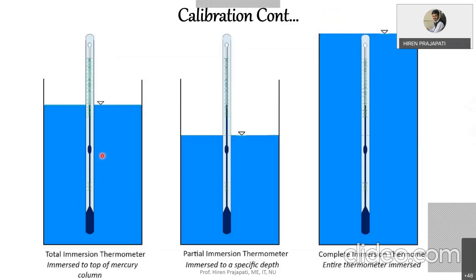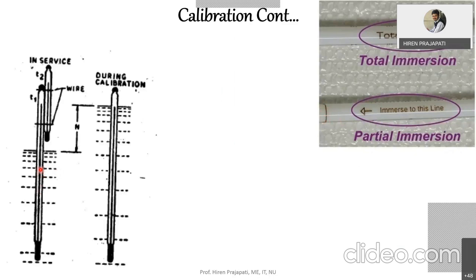These indications are already available on thermometers. For total immersion, you dip up to the mercury column. For partial immersion, you dip up to the reference line. Sometimes, if you are using a complete immersion thermometer but it is not possible to dip it completely — some graduations remain outside — that will give you a wrong temperature reading.